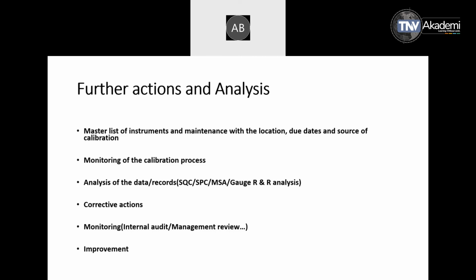So there is a requirement to have a master list of instruments which needs to be maintained with the location, due date, and status of calibration, because that is where the whole monitoring is controlled by the calibration team and the inspection team, and they keep track by monitoring the calibration process. Which instruments are coming due for calibration? Which are the instruments where errors are on borderline? Which instruments need adjustment? Which instruments are of self-calibration status, but the master piece which is given to us needs to be recalibrated because it has been more than a year, because the master testing piece had a validity of 1 year. So all this monitoring is very, very important.